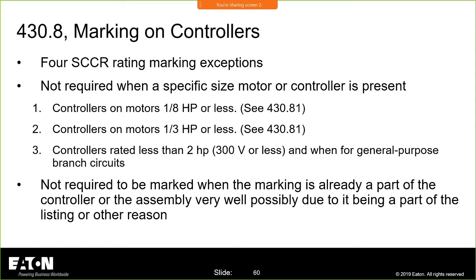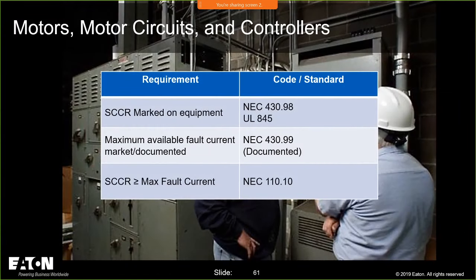And then controllers rated less than 2 horsepower are not required to be marked when the marking is already a part of the controller. All right, so these are your standards. This is your standard. So the marking, this is the recipe. The first part of that recipe is right there. The SCCR has to be marked on the equipment. It's a requirement in 430.98, and it is a part of UL 845.